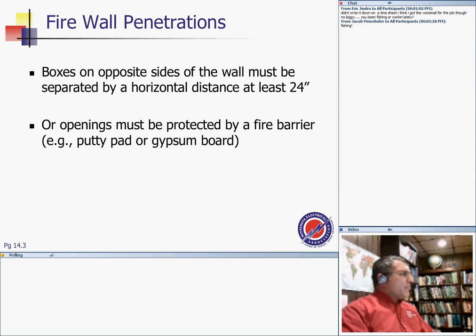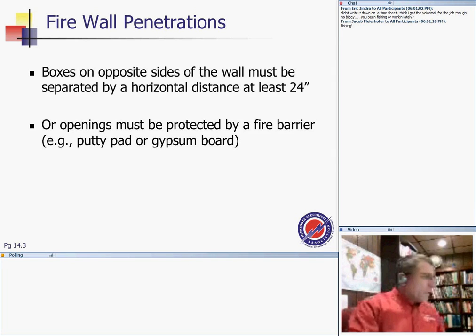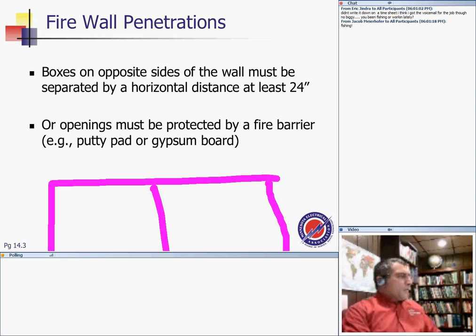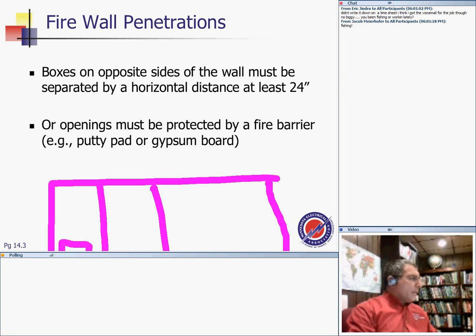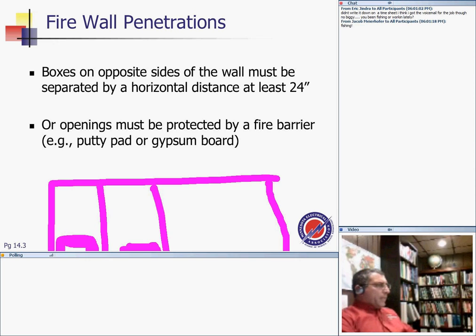Boxes on opposite sides of walls must be separated by a horizontal distance of at least 24 inches. So in a fire-rated wall, guys, here's my studs over here. You will put your receptacle, one on this side and one on the other side, this one pointing the other way and this one pointing this way, right? So we'll put them in 2 different studs in a fire-rated wall, and even if you're going to maintain the integrity of the wall by sealing them, it has to be a fire-rated assembly too, an approved rated wall. You have to maintain 24 inches.